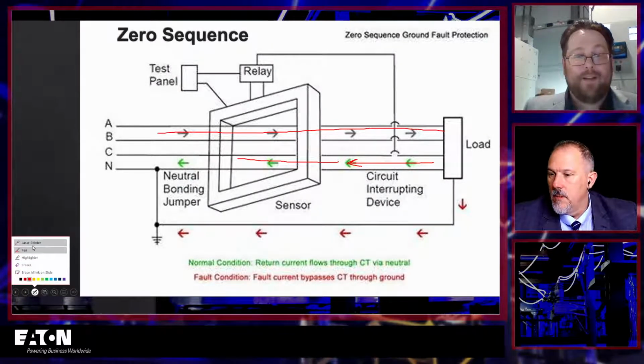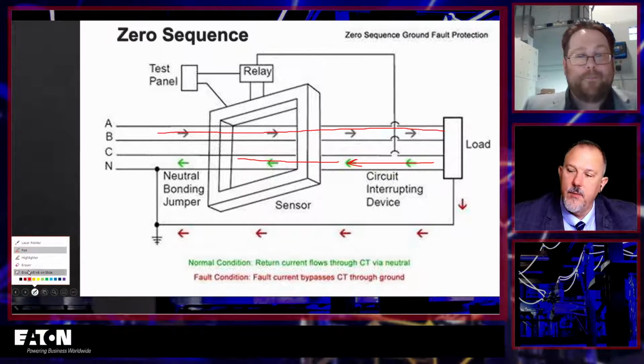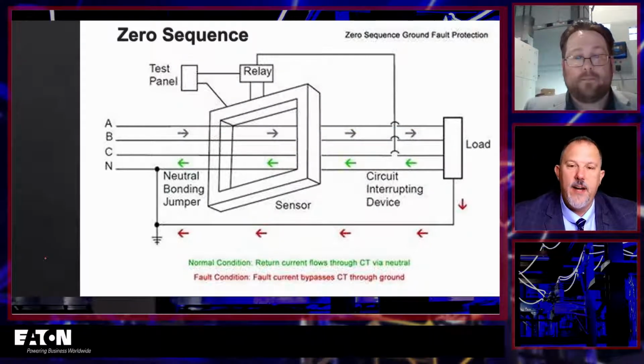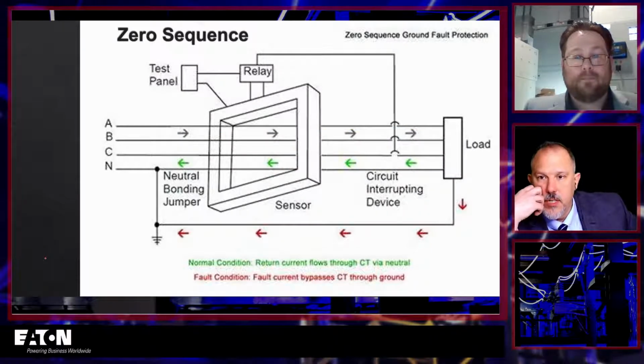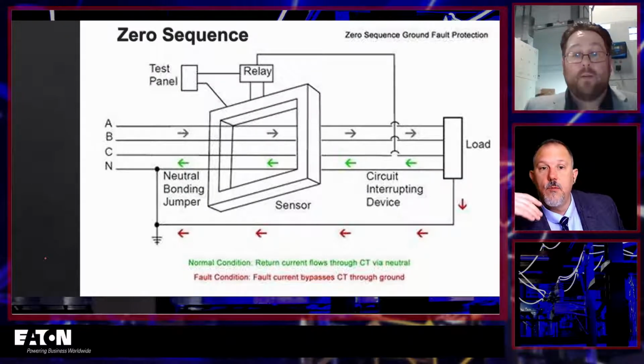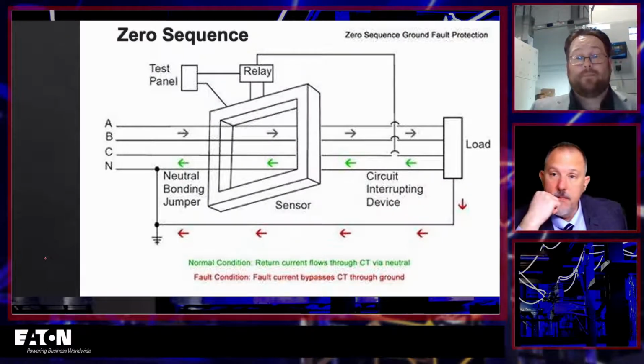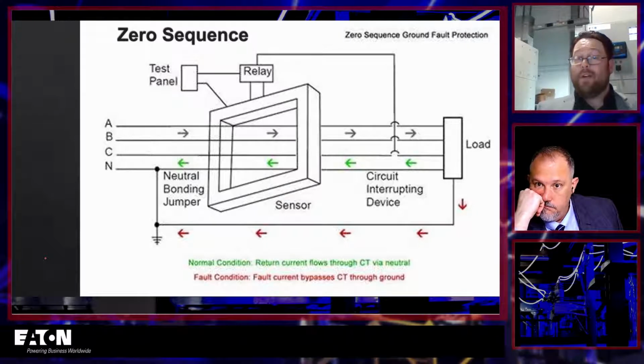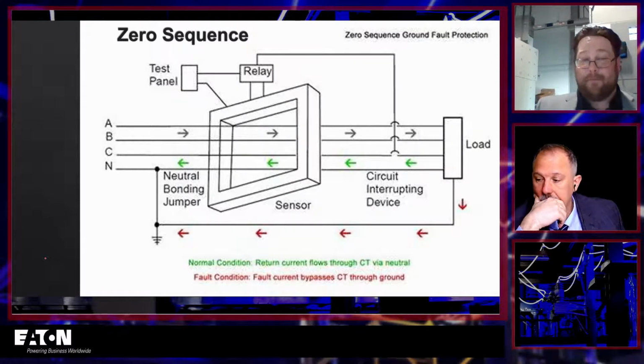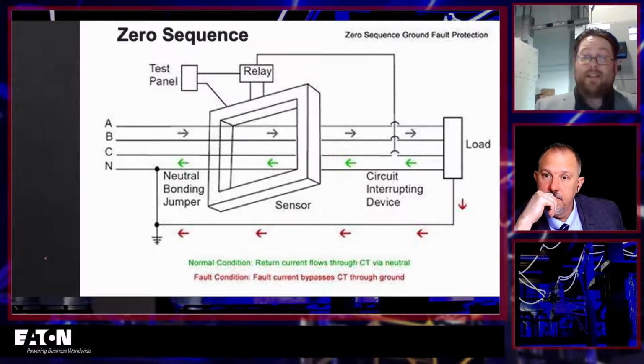Yep. And now, let me ask you a question. Do you have to pull the breaker out to test it? Can you test it while the breaker is in the equipment? So if we're testing the complete system per the code requirement for the first install test, the breaker needs to be racked into the gear. It needs to be in its normal operating state.